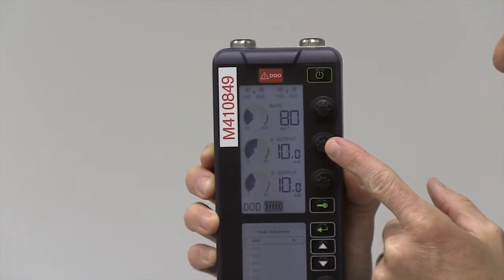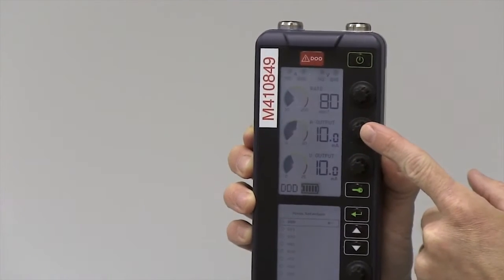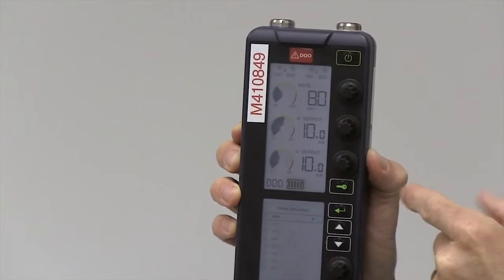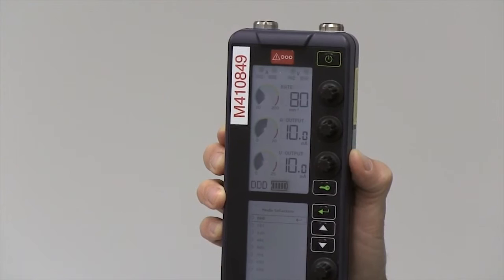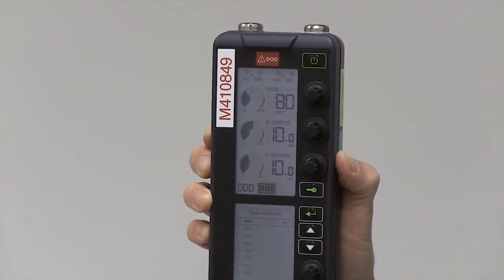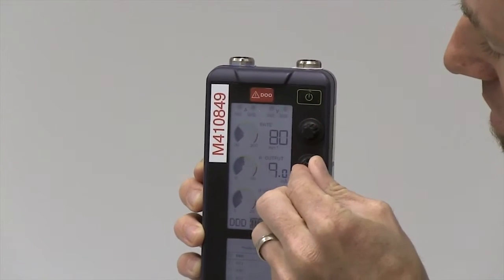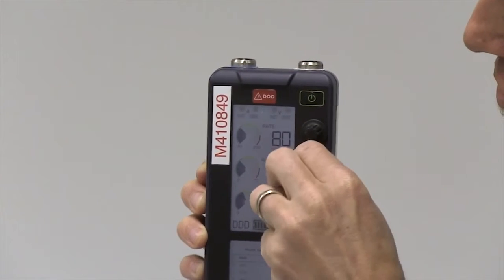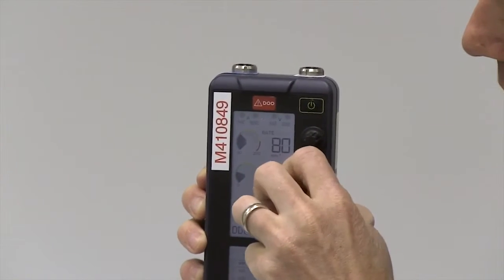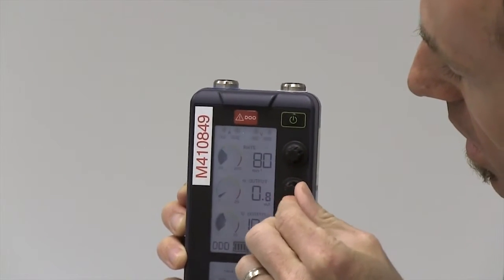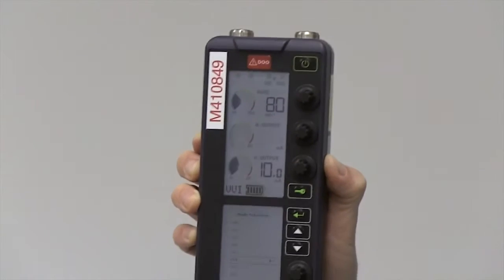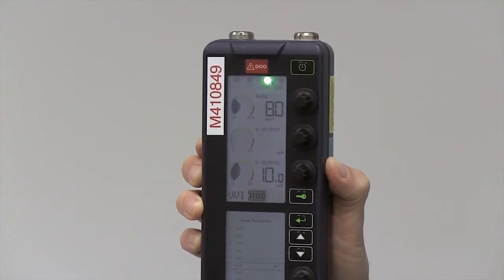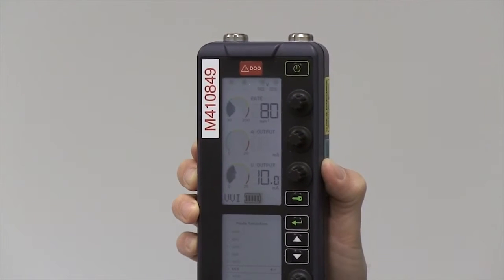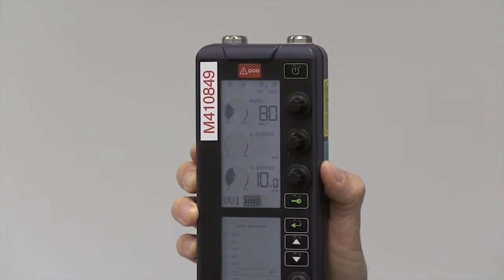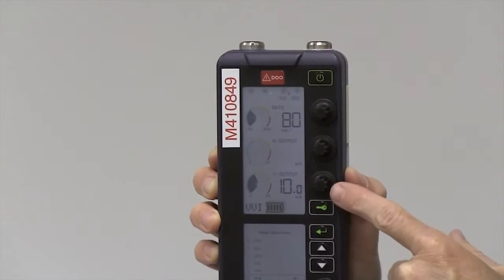The second knob deals with the atrial output. In this case, and for most cases in the emergency department, you want to turn this dial off. And that's going to be turning the dial all the way to the left or counterclockwise until it is 0. The reason that this is important, if you forget this step, you will not be able to adjust the sensitivity of the ventricular output.